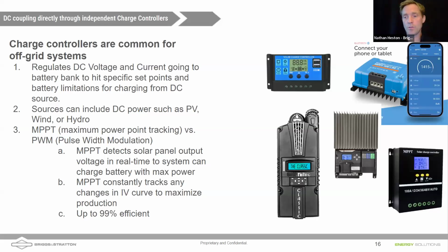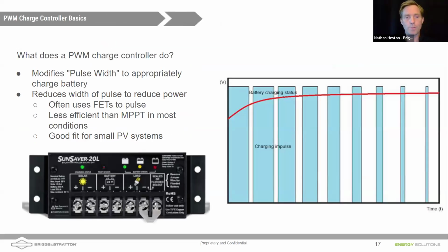But of course, drawing less current, ideally you would want to draw more current to get more power. So what it does is it adjusts the current that it pulls from that solar array up and down and gets the maximum product of current times voltage to maximize production. These can be up to 99% efficient, right? Typically, you get a little higher efficiencies when you're looking at lower power inputs to devices. Once you start powering devices near their limits, you're getting lower efficiencies due to the fact that you've got more resistive heating inside devices where the wiring is smaller.